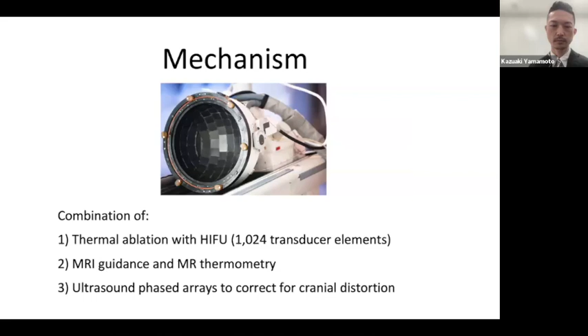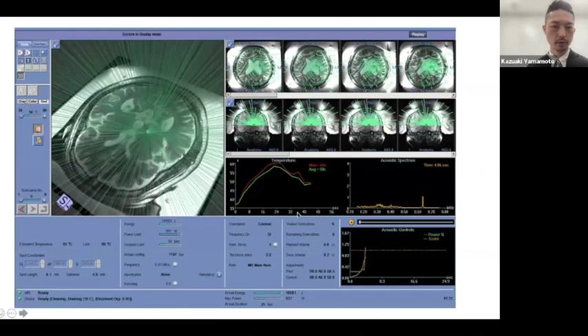In this image, about 1,000 beam paths are visualized in green. MR thermometry provides near real-time feedback of target temperature during each sonication, shown in the center of this figure. And the procedure includes frame application, imaging, target planning, and treatment. After attaching the frame under local anesthesia, we acquire MRI images, plan the target, and proceed with treatment, which includes alignment, verification, and ablation phases.